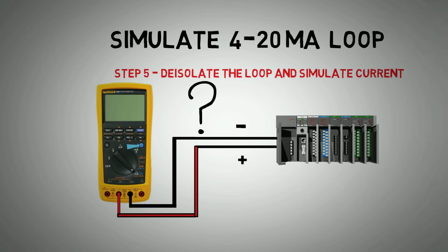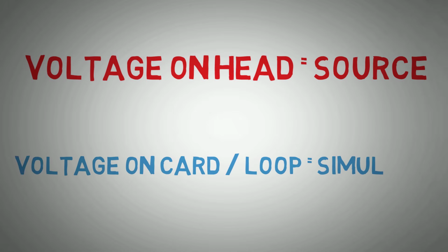If you are unsure if the loop you are working on is source or simulate, isolate the equipment at the head and test for voltage, first on the head and then on the loop. If the voltage is on the transmitter head, then you know you need to source. If the voltage is on the input card, then you know you need to simulate.